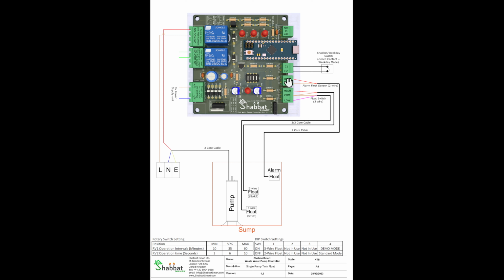Then we have the alarm input, which is connected over here to the alarm float. When it reaches high level, it means that the pump is not able to remove the water, and that will activate the alarm relay. Then we have a weekday Shabbat switch. When the contact over here is closed, it's in weekday mode. When the contact is open, it's Shabbat mode.